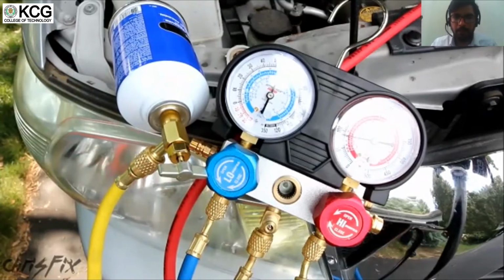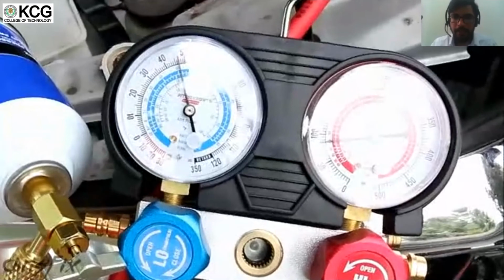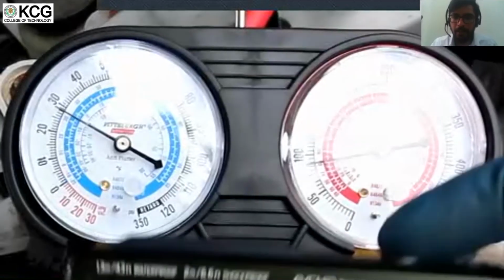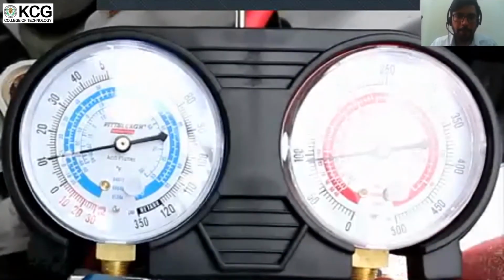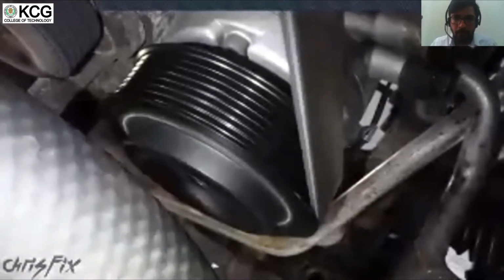You can see the low pressure side drop down to about 10 psi, while the high pressure side is slowly building pressure at around 100 psi. This will increase as we add more refrigerant. If we check the compressor, you can see it's clicked on, which is good. Now we just wait for the compressor to suck out the refrigerant from the can. When you think the can is empty, turn it over and give it another can.